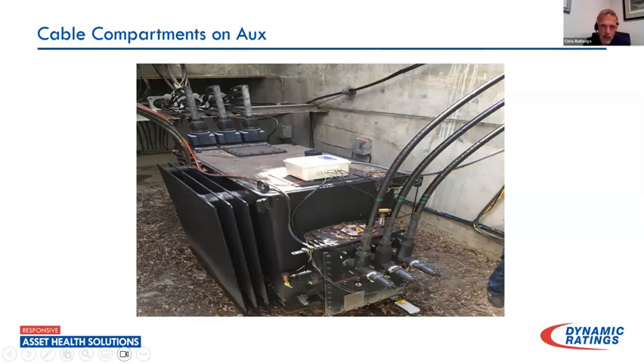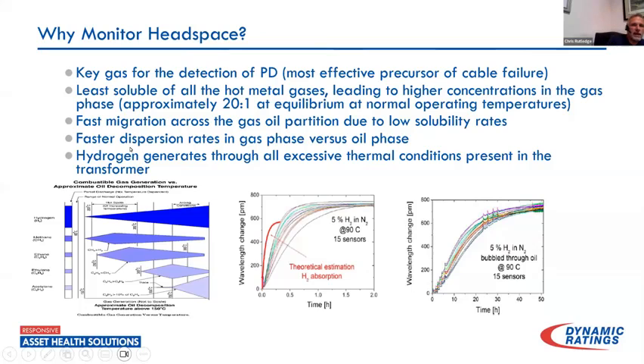This is the unit in service — a bit of a stretched picture, I apologize. You can see the adapter here going into the cable compartment and another one going around to the main tank. That's the general idea. We're using ports that are already available, so we're not really altering the transformer. About an hour to install. So why monitor the headspace? With this type of monitor, I thought about what are our benefits and what are the negatives. First of all, PD was my main target, as cable failure was what I was seeing a lot of.